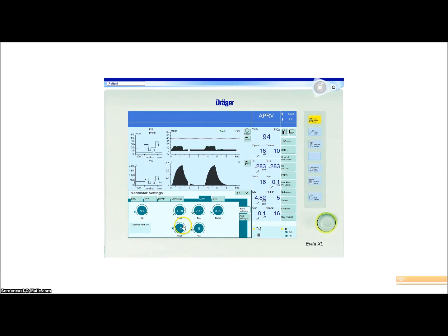Now notice, we have different settings. We have T high, which is, let's go ahead and set that to 3. This is the inspiratory time, which is 3 seconds. And we have T low. That's set to 0.37 seconds. That's the expiratory time. Let's go ahead and increase that to 2 seconds. We're not going to worry about the ramp. We'll talk about that later. We have P high, which is 15.